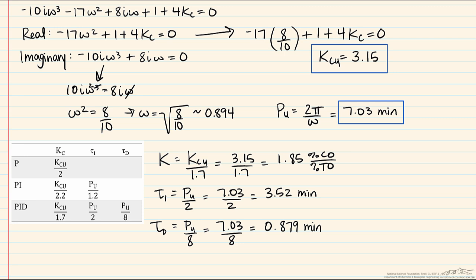An important point to note here is that these parameters are not the be-all and end-all and the perfect parameters for this process. These tuning parameters serve as a starting point for our analysis in terms of where we want to potentially begin the tuning scheme. Another important issue here is that this is tuning parameters for a Ziegler-Nichols, which assumes that the desired response is a quarter decay.